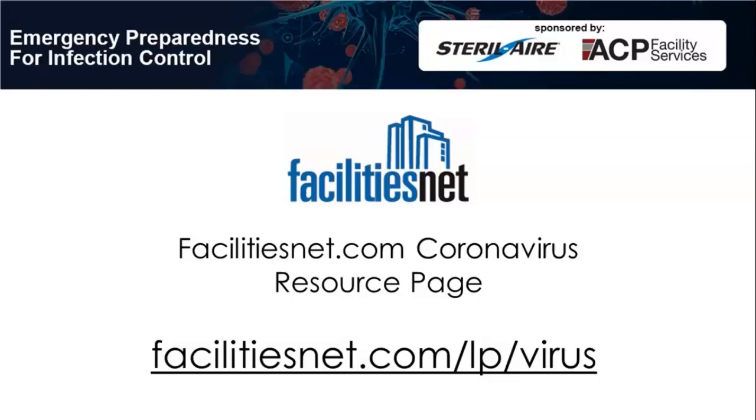A question: is UV protection installed on the supply or return side of the HVAC unit? Downstream, that way you can treat the entire coil all the way back through, and then you get everything as it flies by after that point as well. So you are getting the reservoir of pathogens, and you also get all those pathogens as they fly through. So it creates a control point within your HVAC system for not only that surface we discussed, but also your airborne transmission. And that's also a place where you're going to get air recirculating through your building, so it offers the redundancy of air circulation as well. Okay, great.